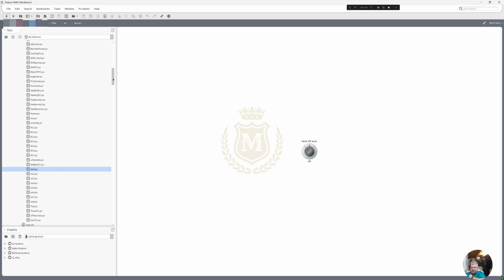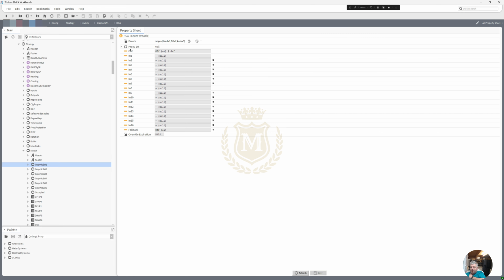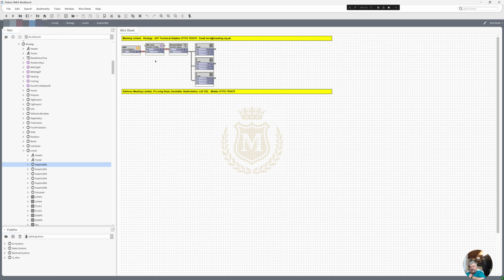And then if I go into the logic for that, which is strategy and switches, graphic switch 1. So this is our normal enum switch. Hand is 1, off is 2, 3 is auto. I've put that into a numeric writable. You didn't need to. You could have actually taken that out of there and put that directly into here. It would do exactly the same. But I put it into a numeric writable. Let me just do a control key Z, control key Z, so I can actually see what the value is.